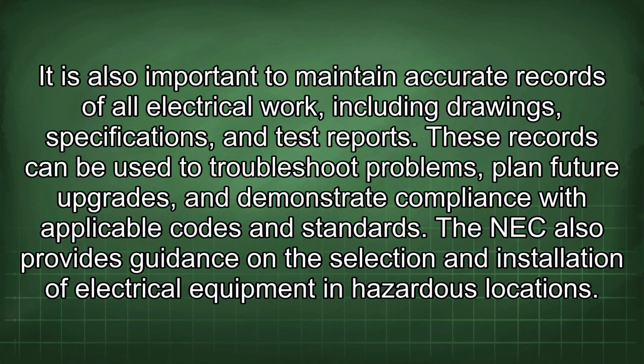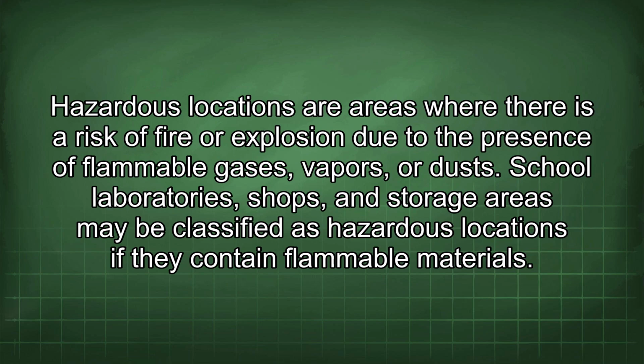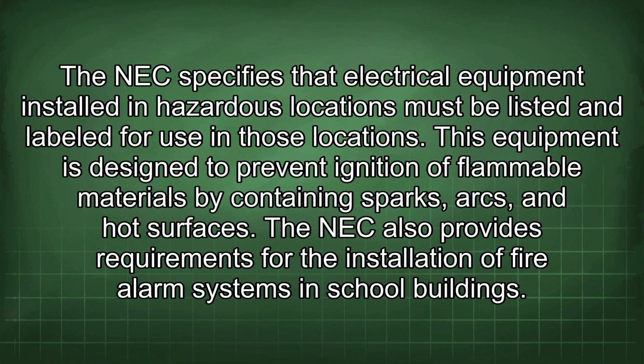The NEC also provides guidance on the selection and installation of electrical equipment in hazardous locations. Hazardous locations are areas where there is a risk of fire or explosion due to the presence of flammable gases, vapors, or dusts. School laboratories, shops, and storage areas may be classified as hazardous locations if they contain flammable materials. The NEC specifies that electrical equipment installed in hazardous locations must be listed and labeled for use in those locations. This equipment is designed to prevent ignition of flammable materials by containing sparks, arcs, and hot surfaces.